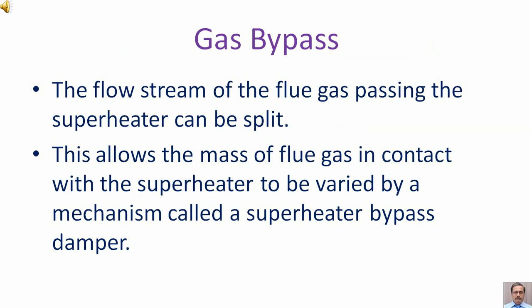Gas bypass. The flow stream of the flue gas passing the superheater can be split. This allows the mass of flue gas in contact with the superheater to be varied by a mechanism called a superheater bypass damper.